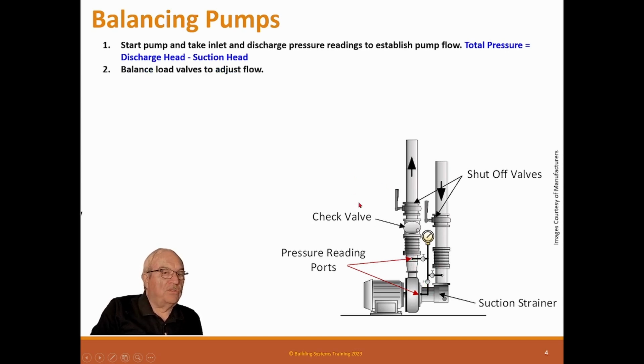So balance: once you get that all set up and it's got the flow you want, then you balance the valves to adjust the flow. So you go out and adjust whatever your loads are, you adjust the flow for that. Now this may be flowing more water than you want, but you go balance the load. Now it's our intention always when you balance the load to use the lowest practical pressure, which means one valve will always be 100% open. That way you know you got the lowest practical pressure. And you balance it so you got it.